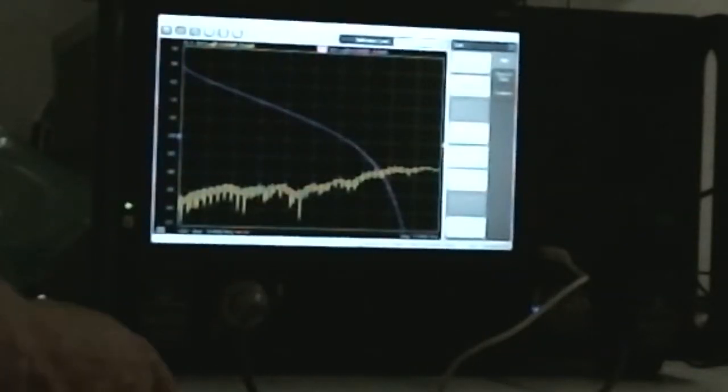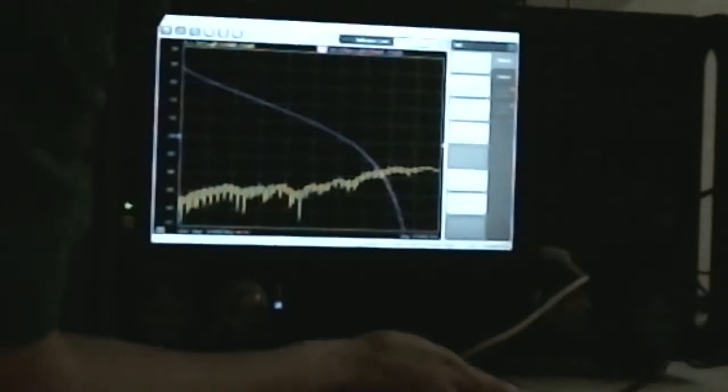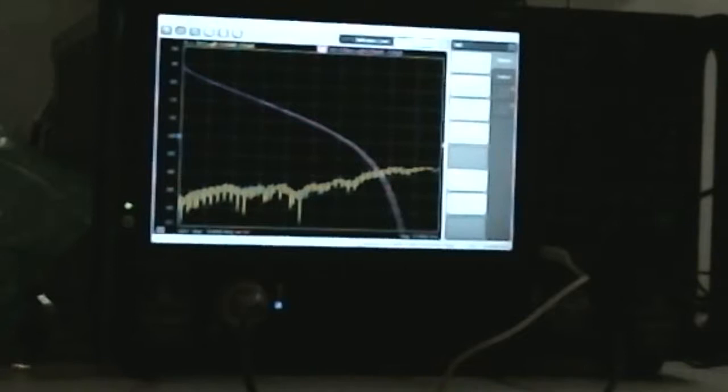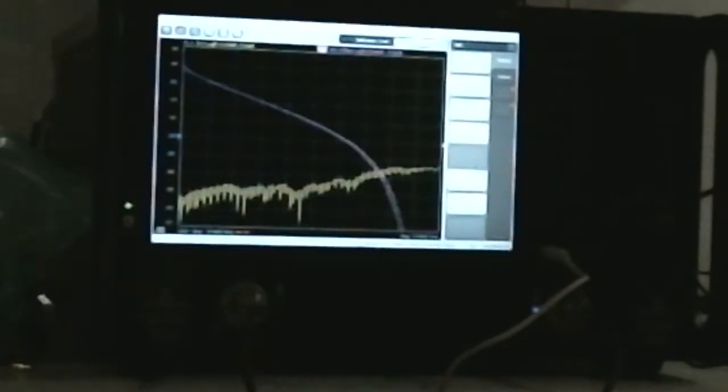And actually, let me do even better. Let me go to data to memory. So I have this in the memory. I'm going to go display data and memory. Okay, so if I bend this and then I go back to it, I may not end up where I am, right? That's the thing: if I do a calibration at a certain position and I come back... How did you save? Oh, I went under math, data to memory, and then I went display data and memory.